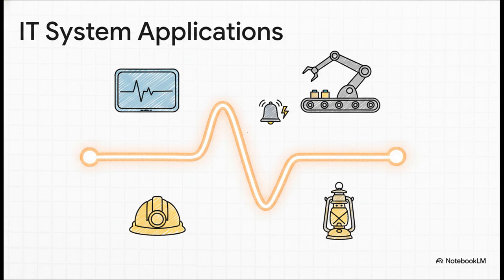So why on earth would anyone want that IT system, the one that doesn't trip on the first fault? Well, because in some places, losing power isn't just an inconvenience. It could be a disaster. Think about a hospital operating room right in the middle of a surgery, or a critical factory production line. You can't just have the power cut out. So the IT system is a genius solution. It doesn't trip, it just sounds an alarm, giving the staff time to find and fix the problem before a second fault would cause a shutdown.